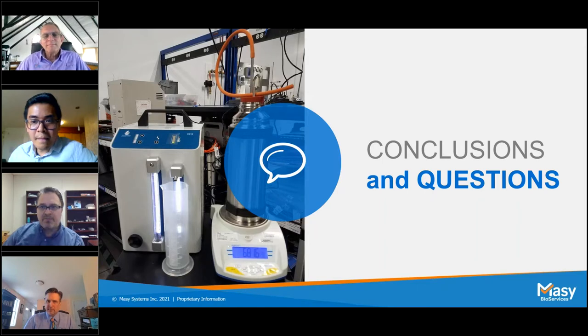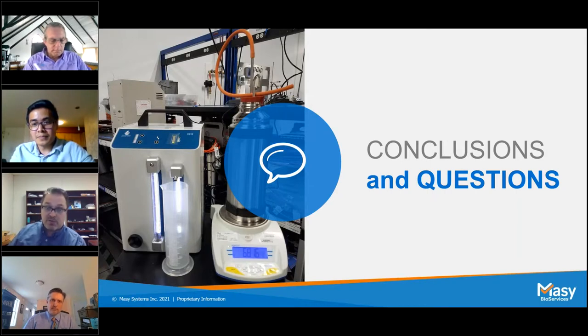I think that's where cycle development is important. So you want to probe each one of those and see what you're looking at. The one thing about having a load probe is that it does not start the sterilization hold until that liquid actually achieves sterilization temperature. What you can obviously accomplish when you have a data logging system is you can set up a load with those different sized containers and respective volumes and see, out of all of those different types, also keeping in mind your warmest and coldest locations in the chamber, right? You don't want to ignore that. Everything needs to be done with that worst case scenario in mind, but you collect enough data so that you understand how each one of those is different in terms of heat up time. And you can look at the data afterwards and build your cycle based on that.